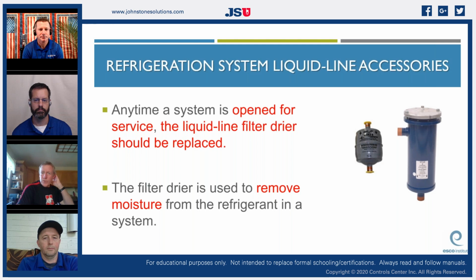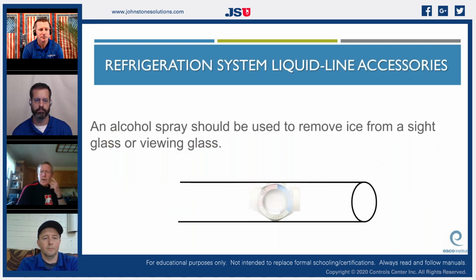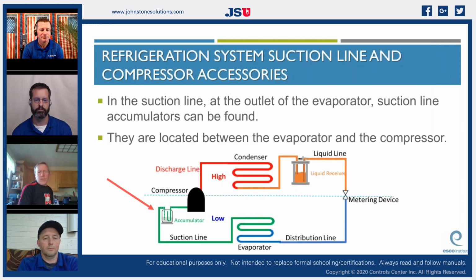Anytime a system is open for service, the liquid line filter drier should be replaced. This should be something you do as a habit prior to pulling a vacuum. It is there to help remove moisture and sometimes other things, like acidity, from the refrigerant. I can't tell you how many times I've seen this on the test. It's okay to use an alcohol wipe or alcohol spray to remove ice from a sight glass. So that's acceptable.